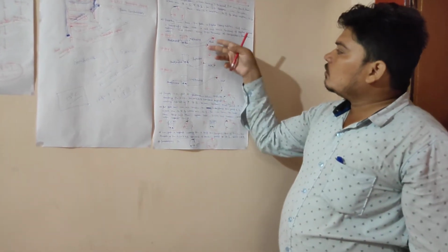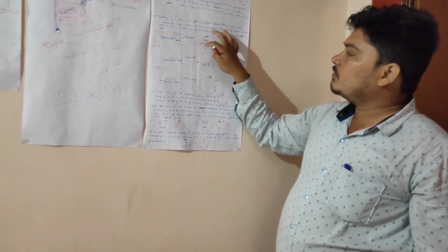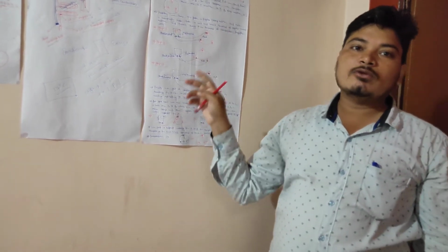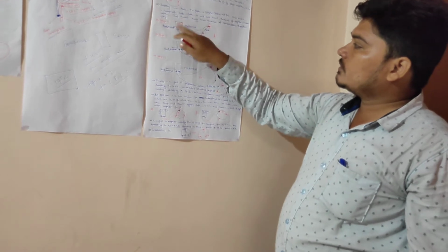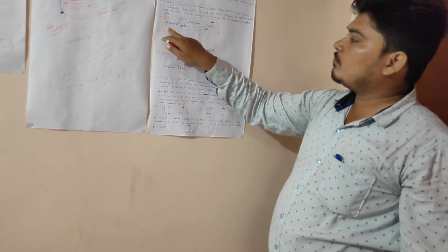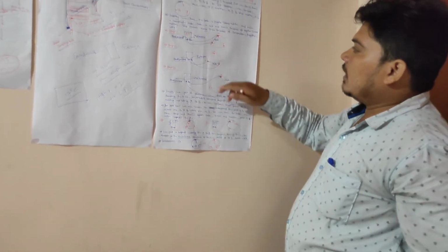One by one, we will read the resistance between two electrical terminals of the compressor. So step 1: take a digital clamp meter which has two electrical wires, one black terminal and another red terminal, and take the first reading between A and B. Between A and B we get 30 ohm.